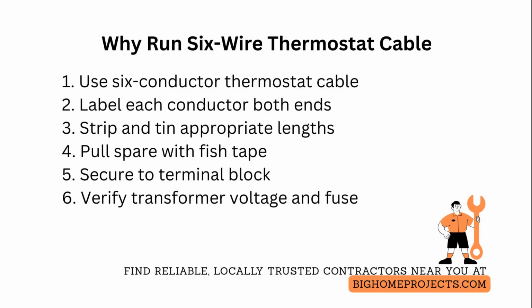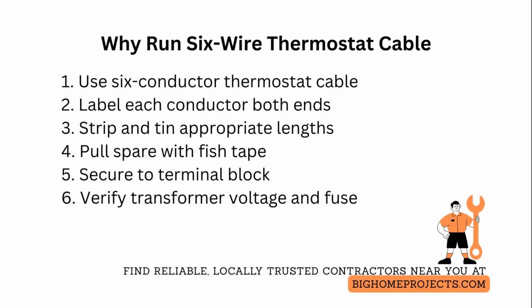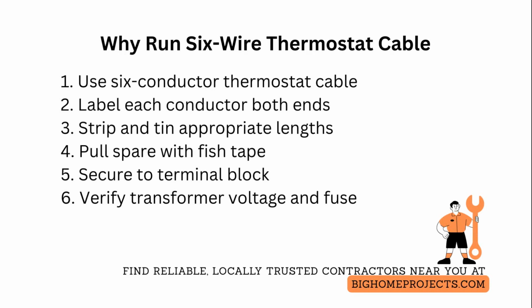Always pull the unused conductor with a pull string secured with tape so it can be withdrawn later without disturbing the existing bundle. At the furnace or air handler, secure the cable to a terminal block rather than bending wires around screw posts. That prevents stress and intermittent connections.